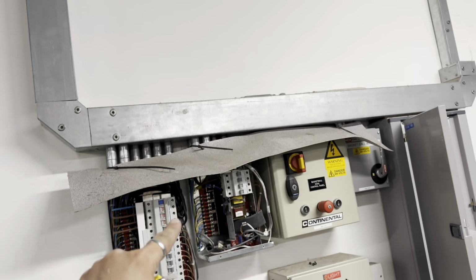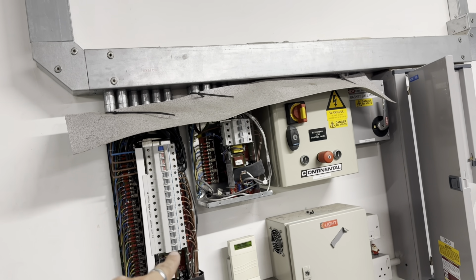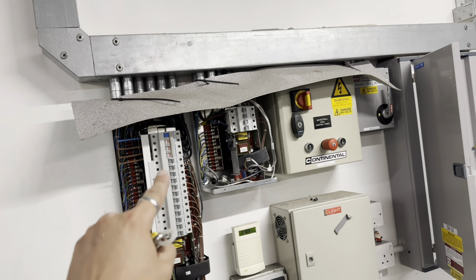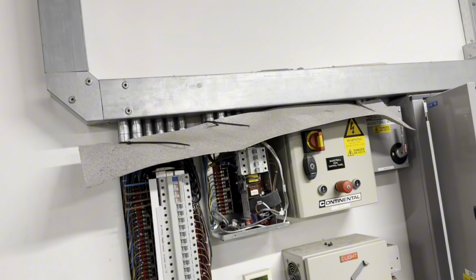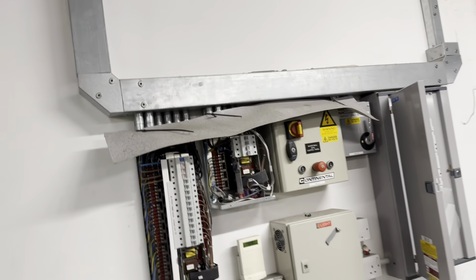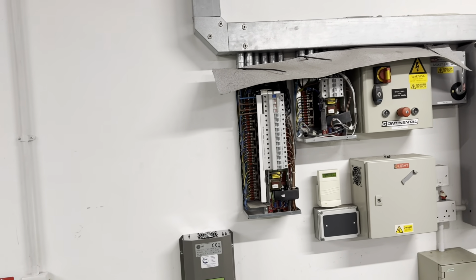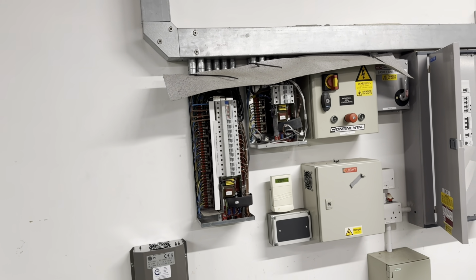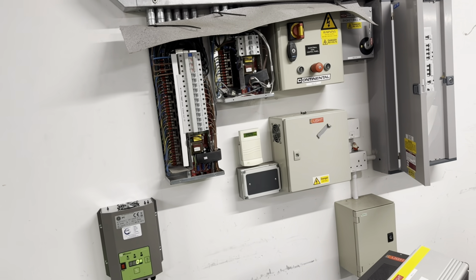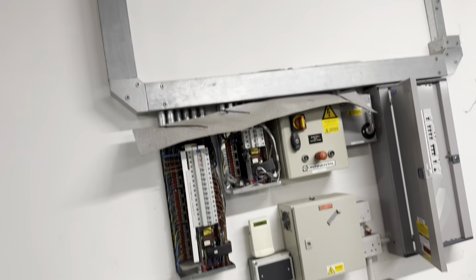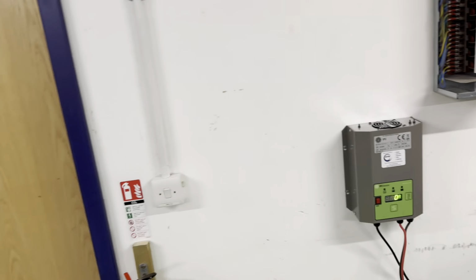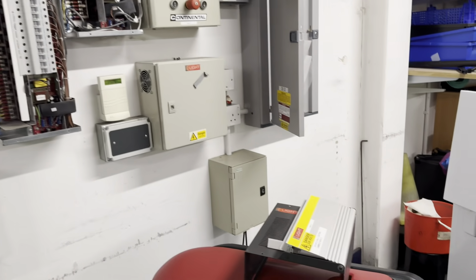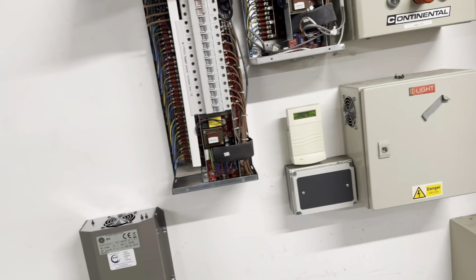We're going to put a big enclosure up here which will house 16 contactors, one contactor for each MCB. There'll also be 2 transformers because we're doing 24-volt switching, utilising some of the cabling that already goes out there for the key switches. So we're going to use 24-volt key switches, which will bring in the coils of the contactors to turn the lights on and off, because at the moment it's on a smart dimming system that doesn't work properly, so they want to get rid of that.